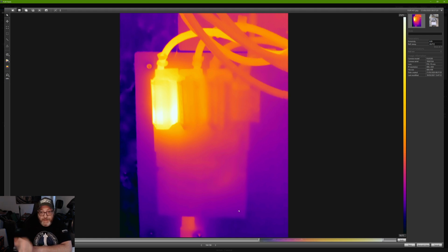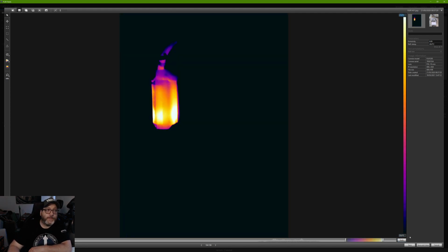I can bring the baseline of the image up to an area that better represents the narrower area that I want to measure from, but that will make a lot of the image black. So let's say, for example, I was only interested in temperatures from 25 degrees. Okay, I could change that to 25. Now everything in this image is a representation of anything that's 25 degrees or above. Okay, it's a bit more of a contrast on the fuse.